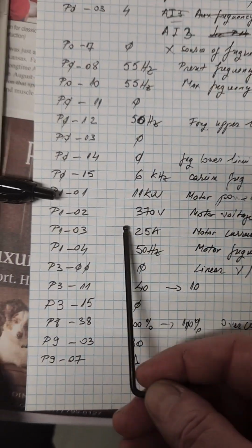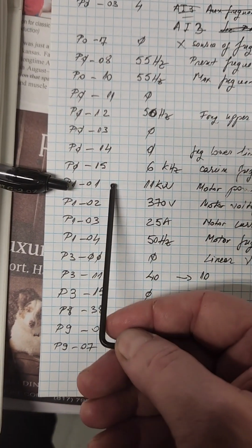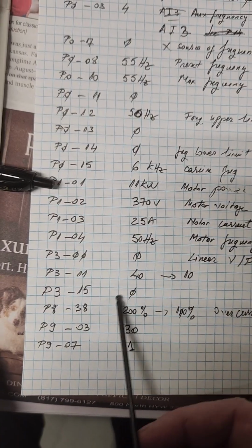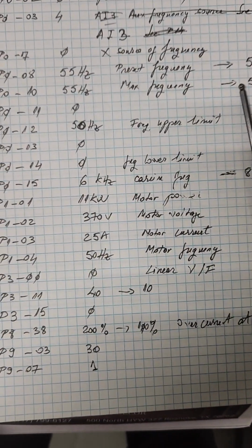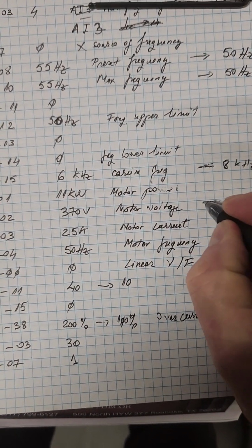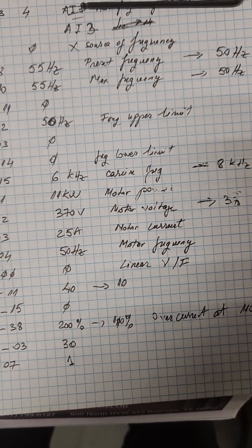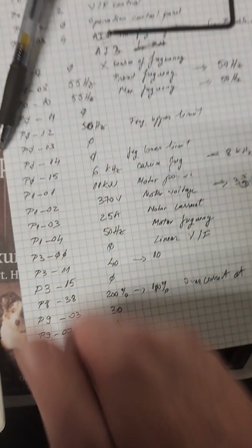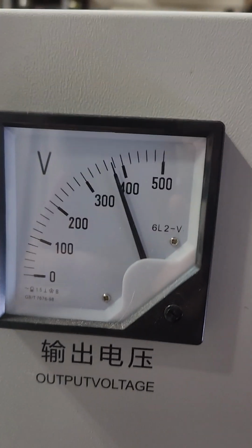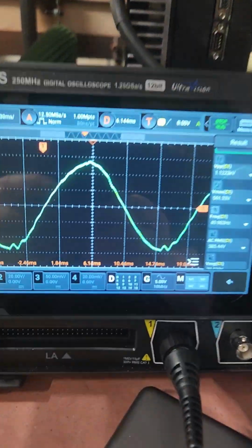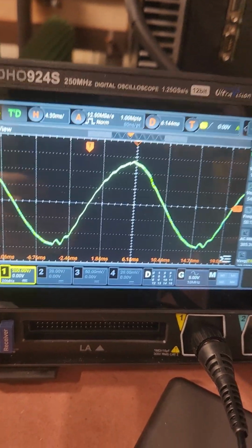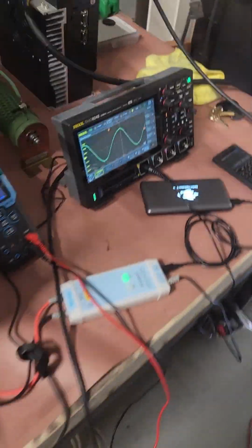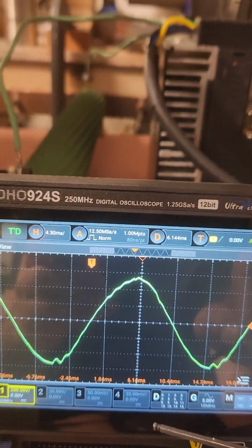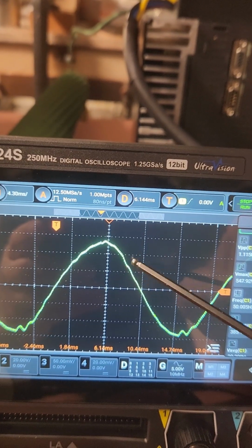So what I did here, these were the motor setting like you would power a motor: 11 kilowatt, 370 volts, 25 amps, 50 hertz. I changed this to 360. I made it smaller, right? So that's changed to 360 volts. Goddamn pen. Okay, so let's look what we have now. So you see the voltage is lower now, right? And it's the waveform now. I mean, looks better. I don't have that. Let me get a pen. With this carrier frequency changed to 8 kilohertz, I don't have the ripple here, that undulation. I have it here now.